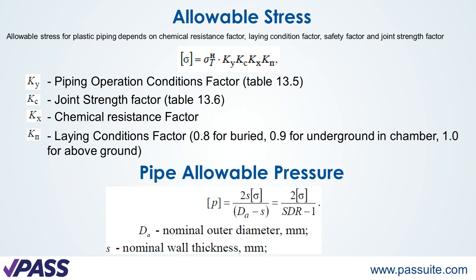The allowable stress is multiplied by several safety factors. The first factor is the piping operation conditions factor, the second is the joint strength factor, the third is the chemical resistance factor, and the fourth is the laying conditions factor. For example, it equals 0.8 for buried piping, 0.9 for underground piping in a chamber, and 1.0 for above-ground piping.